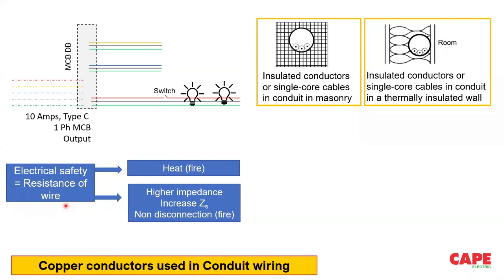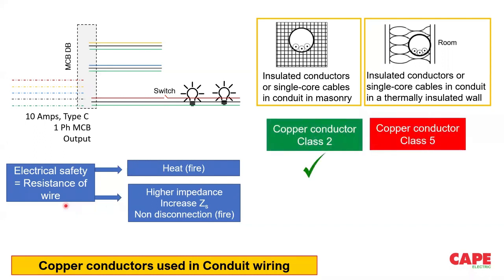conductor resistance is important, because if the resistance of the wire is high, more heat is produced. In that particular case, wires are classified into class 1, 2, 5, 6. Class 2 and 5 are flexible wires. All the calculations in the standards are made based on copper conductor class 2. Now, I am showing class 2 and class 5. Class 2 is a copper wire with lesser resistance, 8% or 9% lesser resistance. Class 5 is a copper conductor with higher resistance. This means a class 5 wire with higher resistance is more dangerous in comparison to a class 2 wire. All the calculations are made based on class 2 wire. All the conduit wirings we are supposed to make with a class 2 wire.